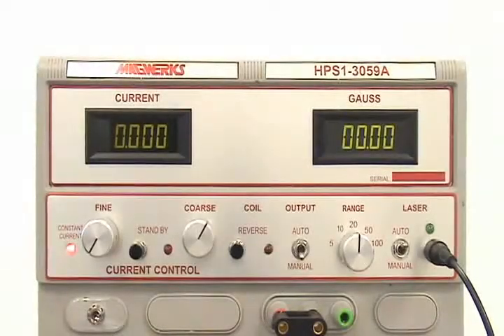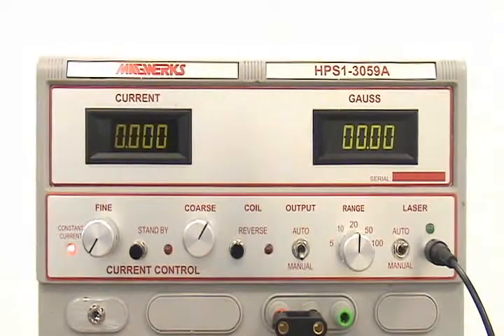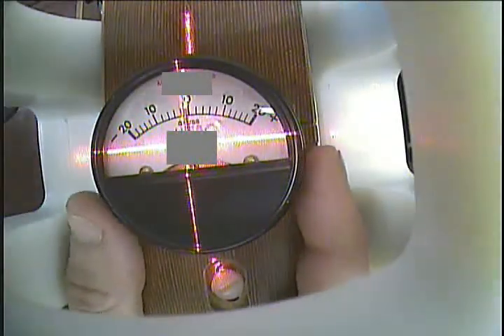In less than five minutes the test is complete. Any magnetometer in the market today can be checked just as easily. Now we will demonstrate how to operate the system manually when magnetometers fail the automatic test to figure out just how far out of calibration they are.